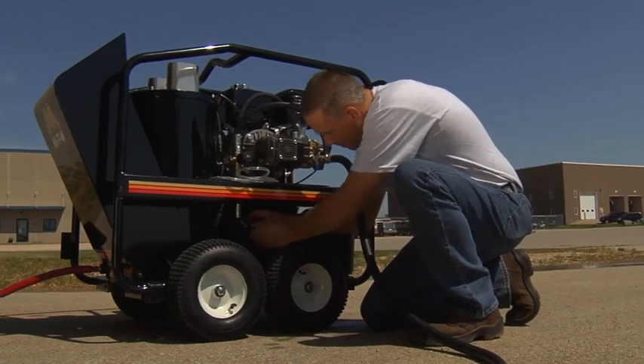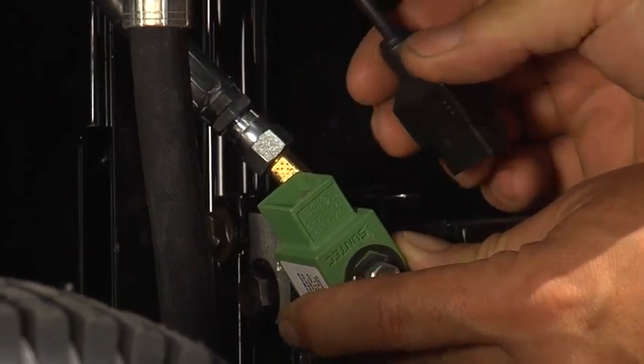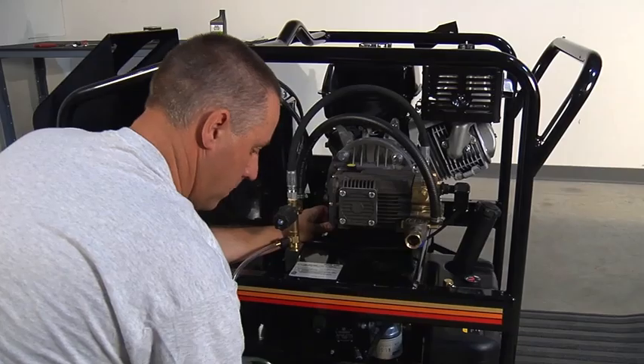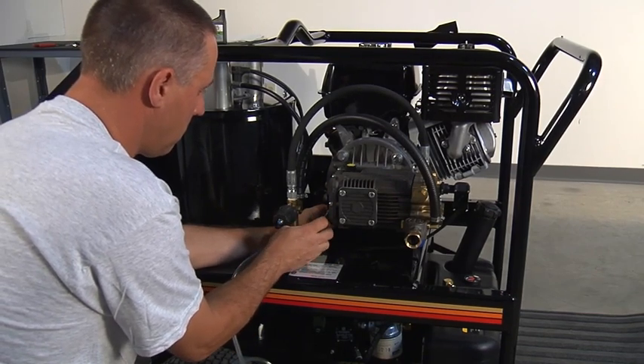With the trigger gun released and the burner still firing, first unplug the fuel solenoid wire from the fuel solenoid coil. If the burner continues to fire with the wire unplugged, then the fuel solenoid piston and coil assembly must be replaced. Contact a qualified MI-T-M Service Center or the MI-T-M Technical Services Department for assistance.